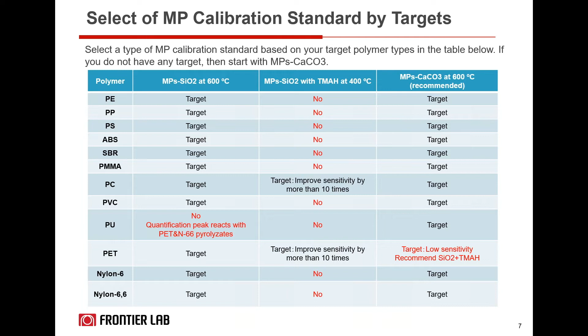So now moving on to the other parts of the system configuration, the UA MP column kit, which is Ultra ALLOY. UA stands for Ultra ALLOY microplastic column kit, which consists of a separation column, a UA5, that's 5% diphenyl, 95% PDMS, a pre-column that we call UA pre-column 50, which has a medium polarity, and also a UA connector. This kit, everything including the column and the pre-column, really improves the accuracy of qualitative and quantitative analysis of plastic mixture samples using F-Search MP 2.0. Also, this product reduces the contamination of the separation column, thus reducing the replacement frequency of your column.